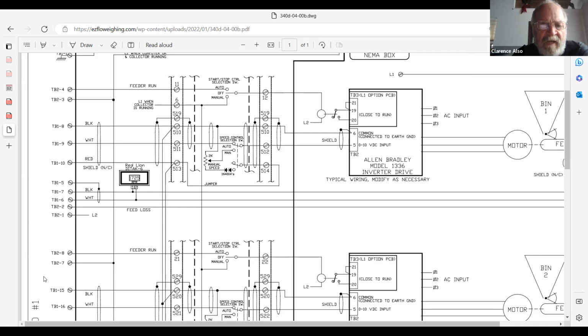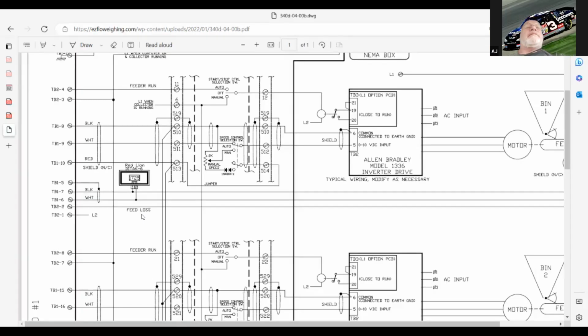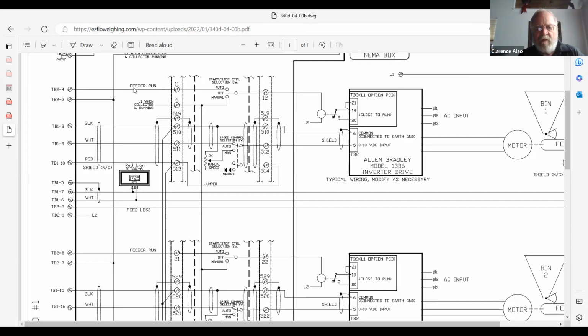So let's look at TB 2-4. This here says like feeder run, and we've got to energize a relay for that. We have a choice of whether we're going to energize that relay automatically or manually. If you have a switch in the automatic position, TB 2-4 is going to have 120 volts when the computer says we want it to be on, and then it's going to go out there to that. So it goes to TB 2-4, which is right here. If you guys aren't following me, if you can see my thing, it's got 120 volts here.